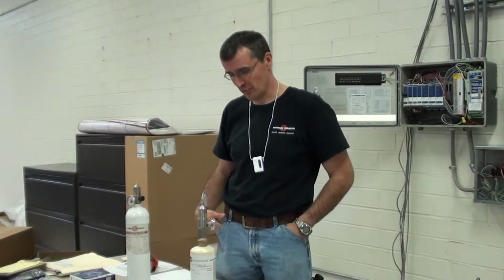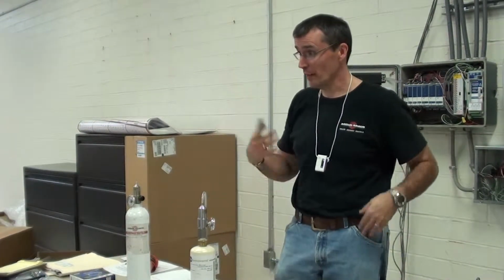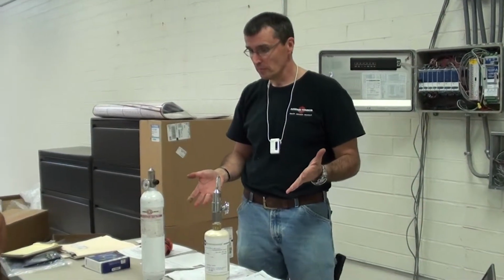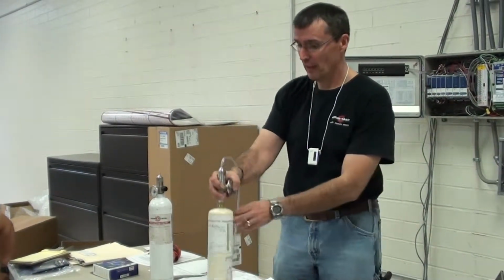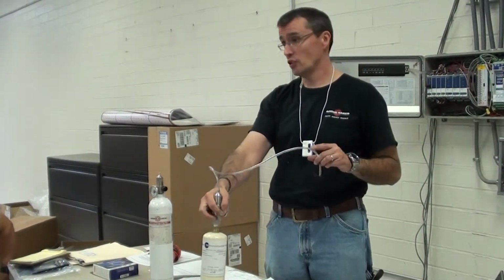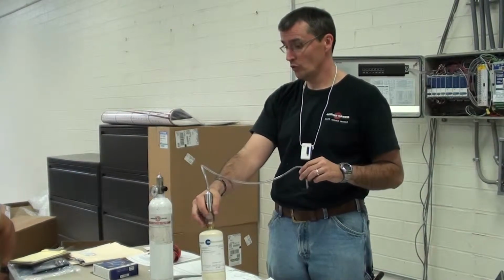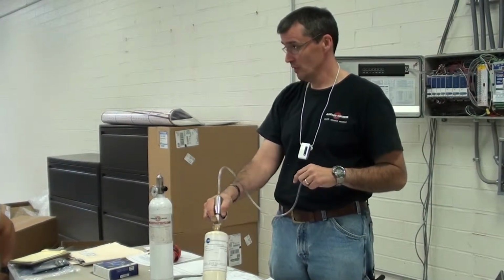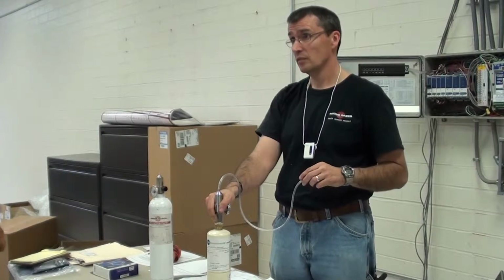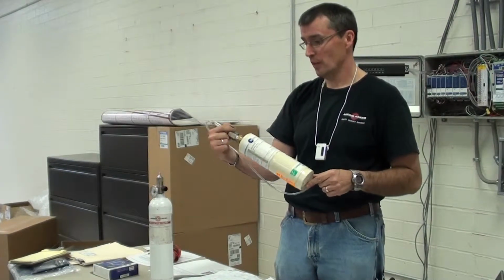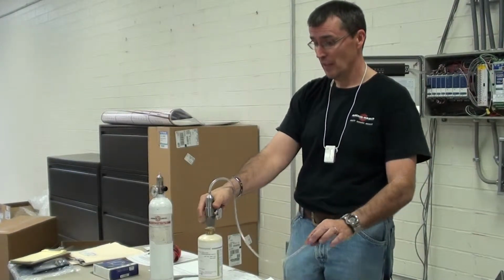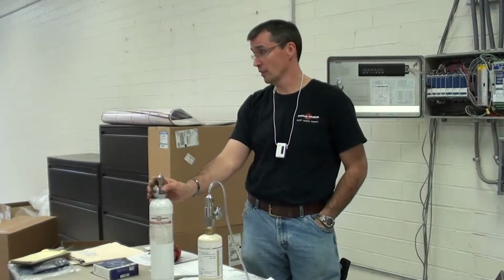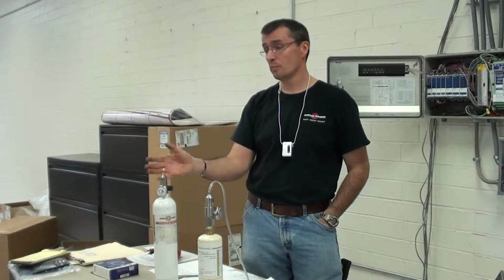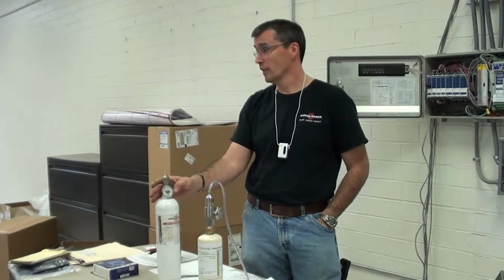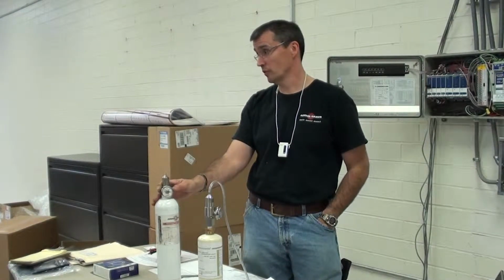You're live. Okay. All right, so we're talking about calibration now in your Xgards. So we've talked about the fact that because of the gases that you have present, we're going to use 50% propane, LEL, pentane, sorry, thank you for correcting me, 50% pentane, and we're going to set your output to be 35% LEL. Just in case you don't know what percent LEL stands for, it's percent of the lower explosive limit.